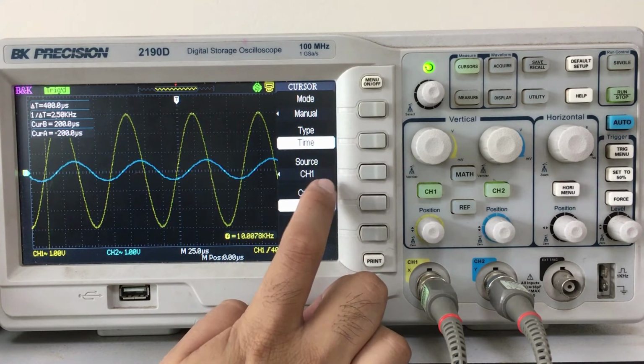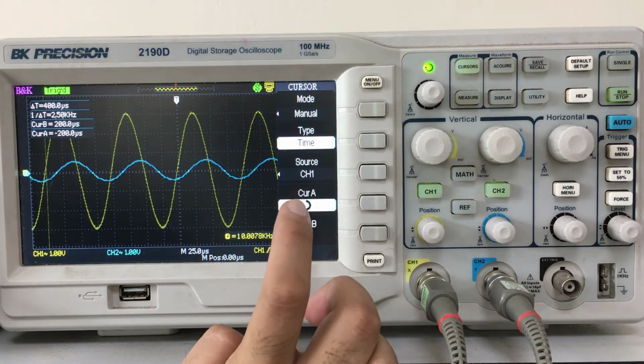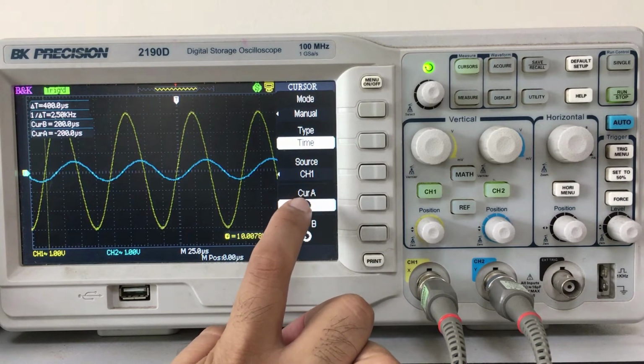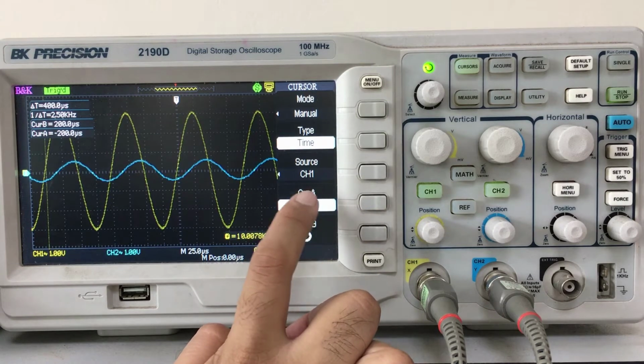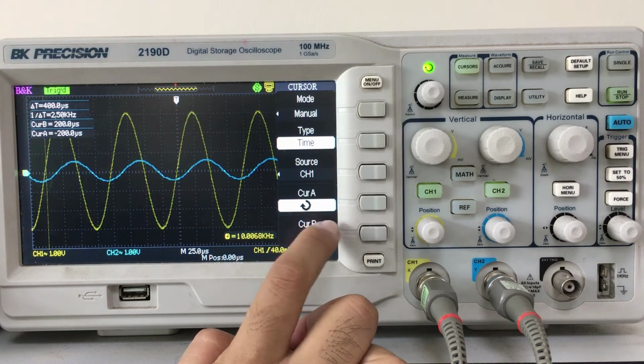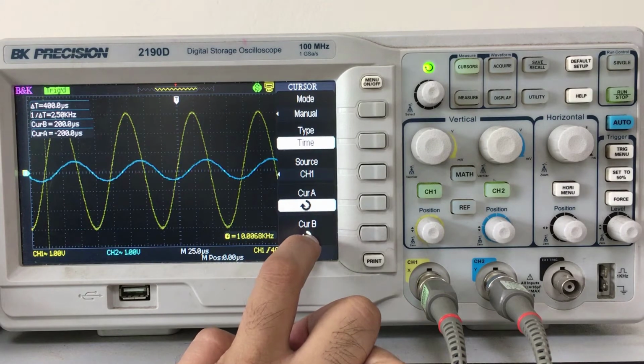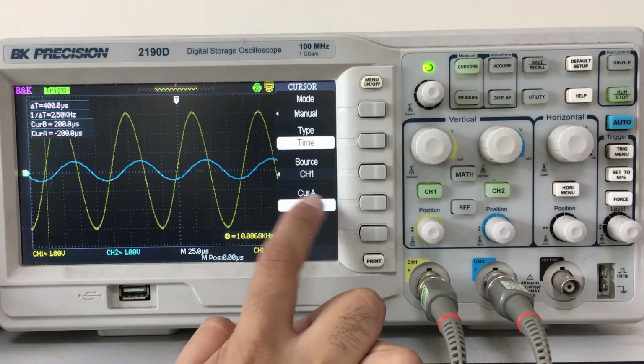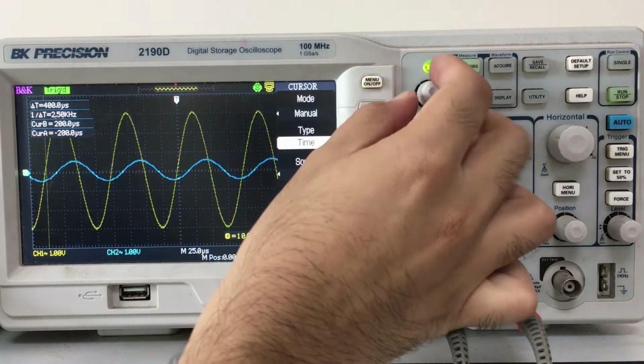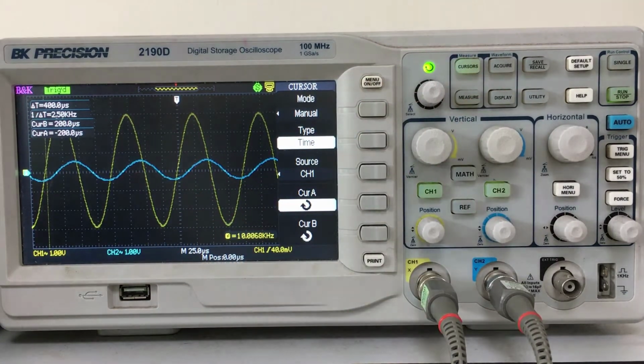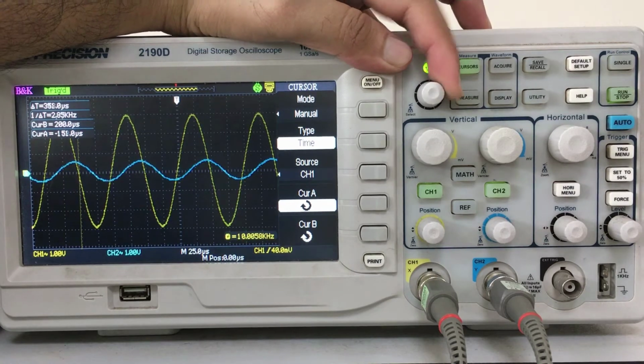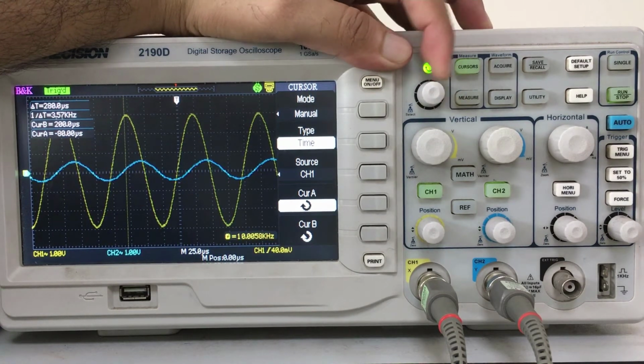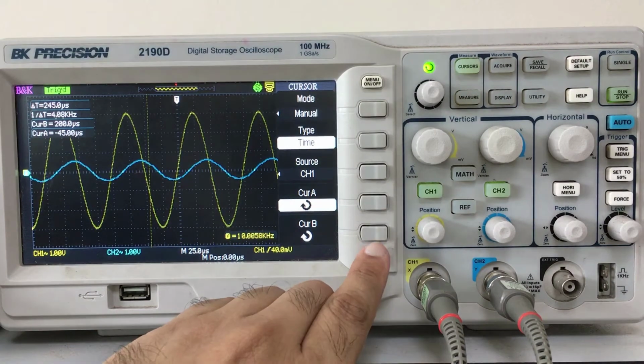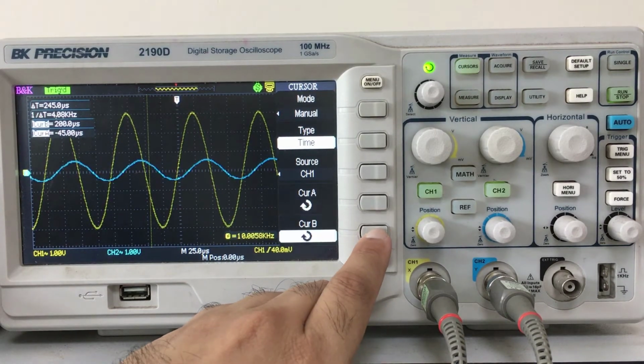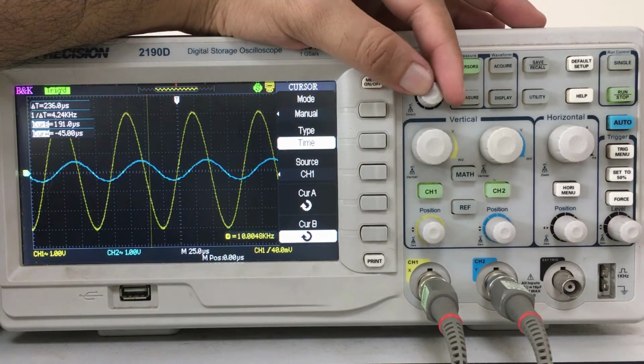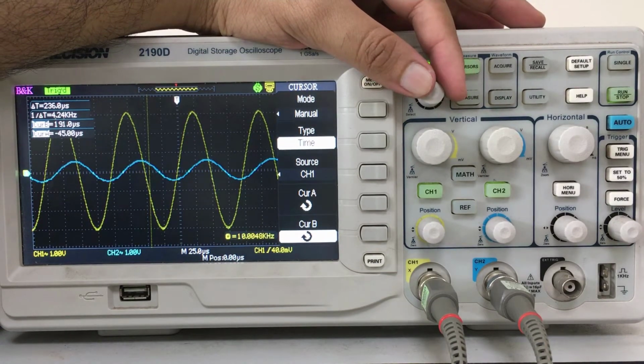Now the type is time. Source is channel 1. Since we are measuring with respect to the source voltage, we should keep the source at channel A. Now you can see that we have two cursors, cursor A and cursor B. When cursor A is selected, represented by this white highlight, if we rotate this universal knob, one of the cursors will change its position. By selecting the other cursor B and rotating this knob, we can manipulate that other cursor.